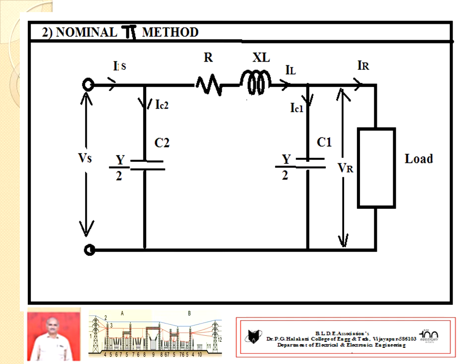IC1 and IC2 are the currents flowing through the capacitances. IC1 flows through the capacitance nearer to the receiving end side; IC2 is the capacitance current nearer to the sending end side. IR is the load current or receiving end current. Voltage VR is available across C1, so by knowing VR you can determine IC1. From the load condition of power and power factor, you can calculate IR. The vector sum of IC1 and IR gives line current IL. Then VS equals VR plus the voltage drop of the series impedance, that is IL times R plus j·XL, or IL times Z.